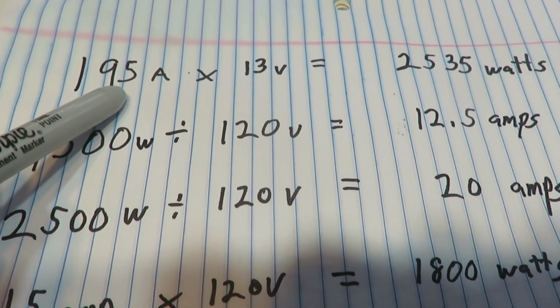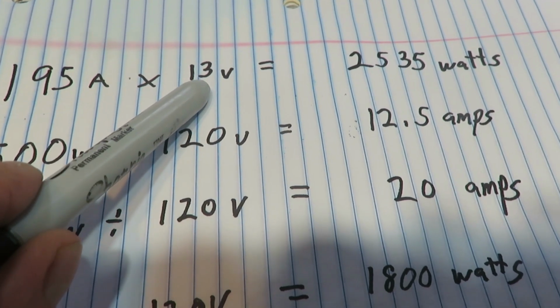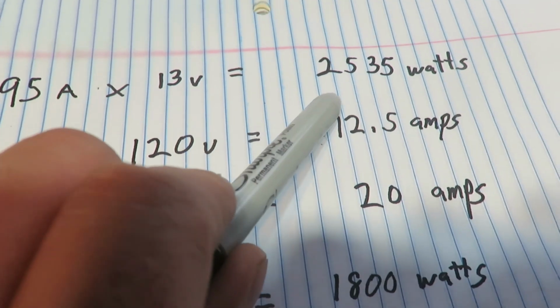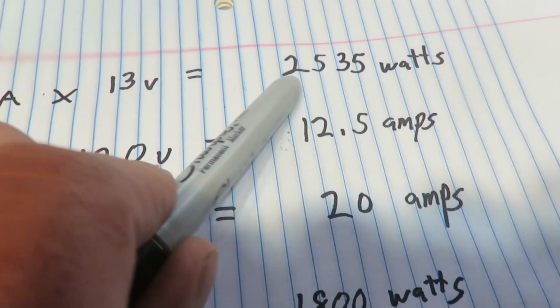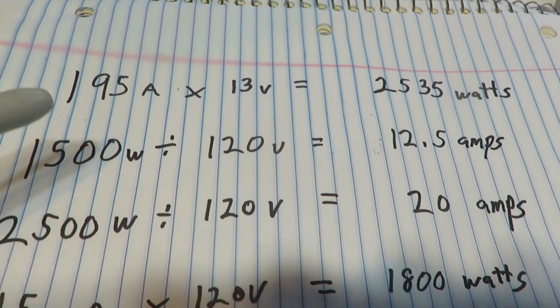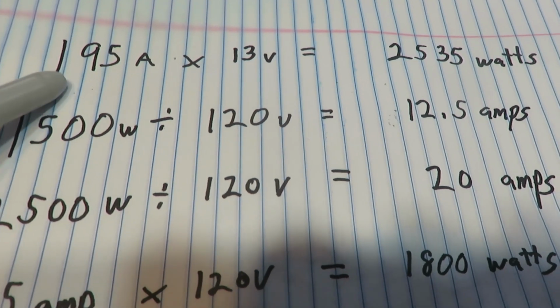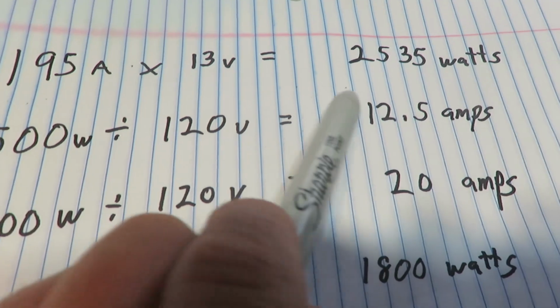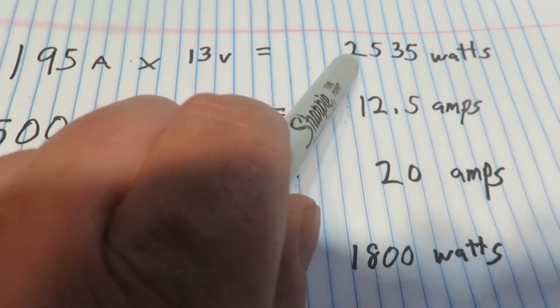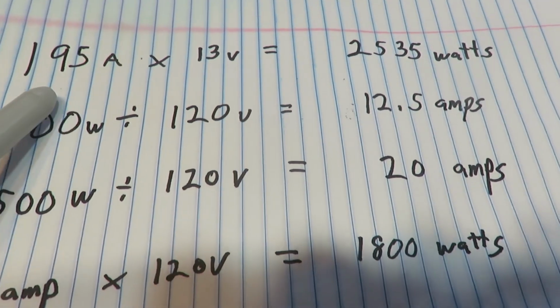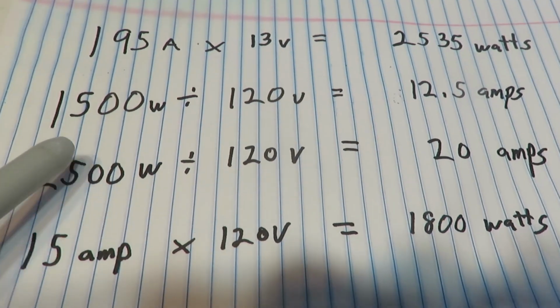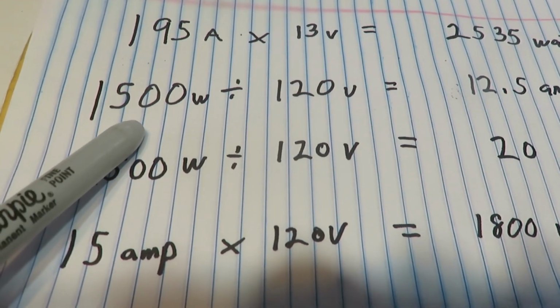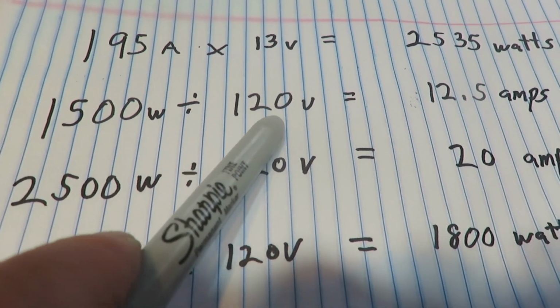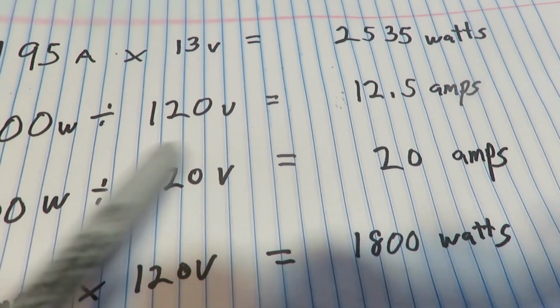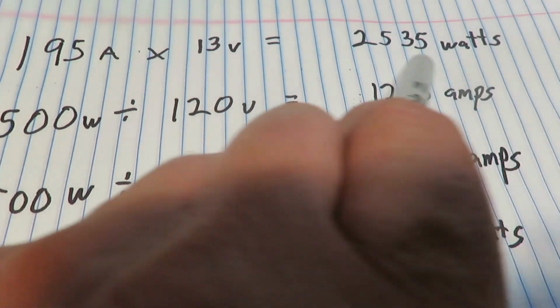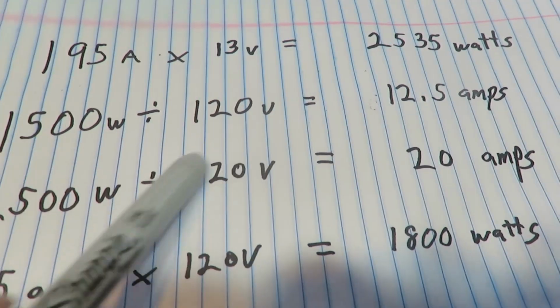We had 195 amps, and if you multiplied that by 13 volts, it drops to around that, or 12.8. That's 2500 watts. So I guess you could theoretically put a 2500 watt inverter on this battery and stay under the 200 amps. Of course, that would be with just resistance loads, and you're not taking into account the inefficiency of the inverter and the battery, your cabling, some drops you'd have. Anyway, 1500 watts, the inverter I was using, divided by 120, that's 12.5 amps. So that's kind of what they rated on, because a typical 15 amp circuit in a household, they don't usually go over that for most appliances.